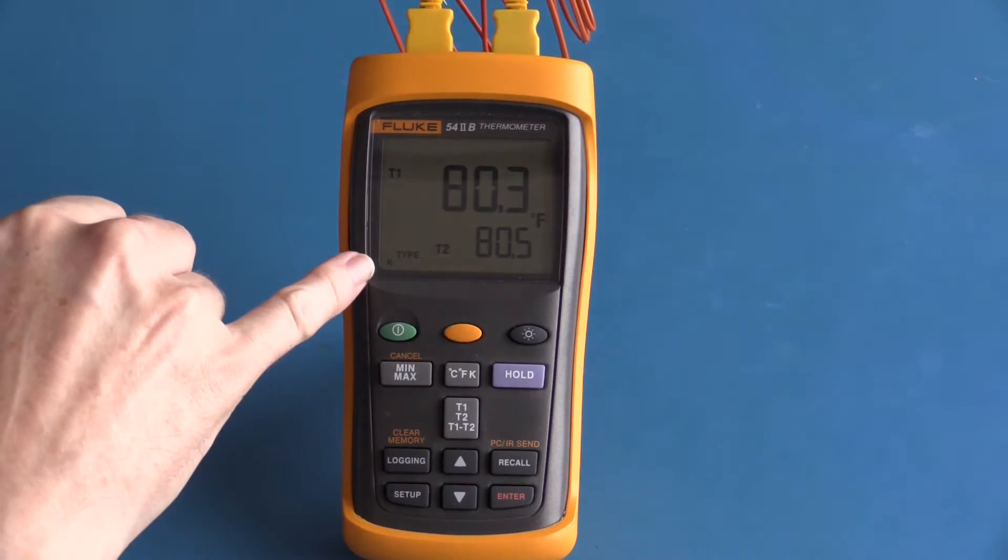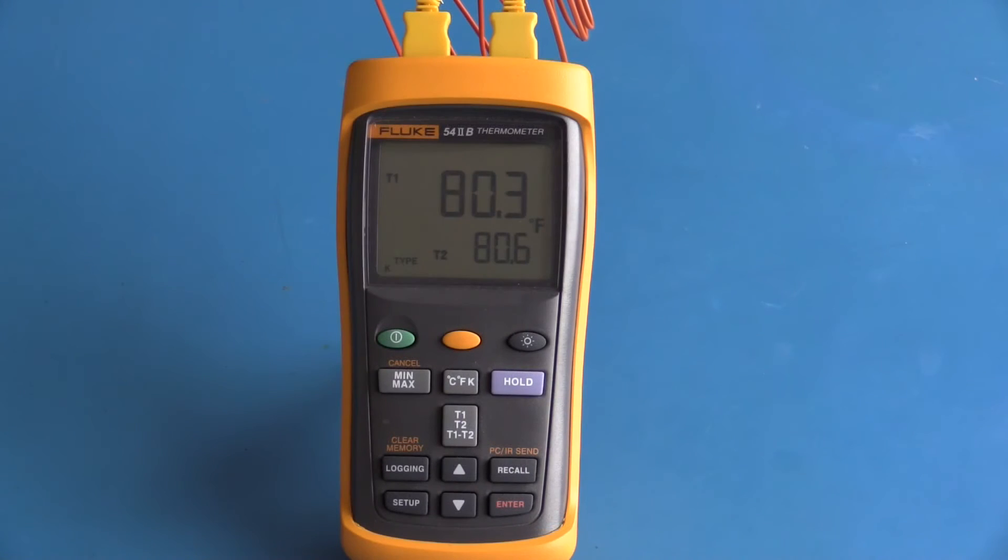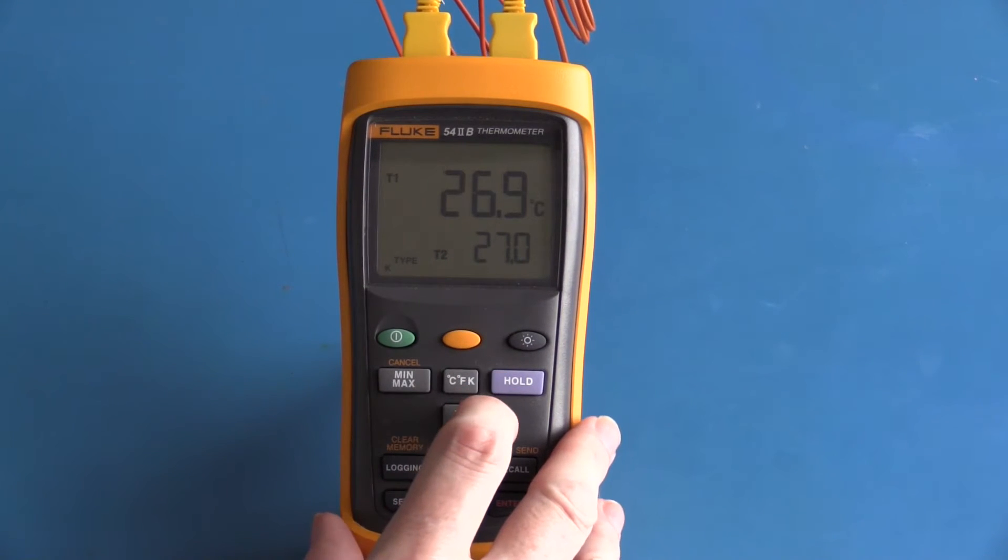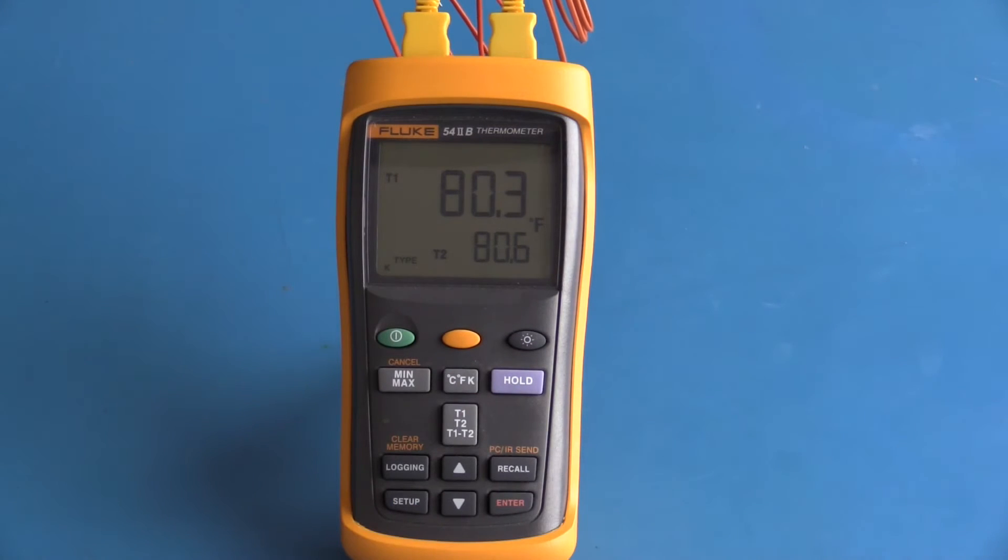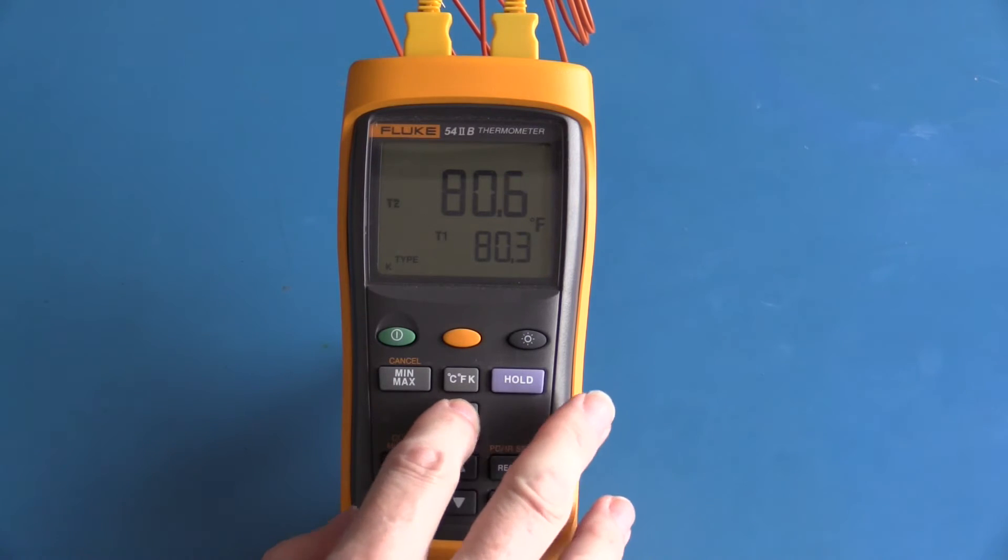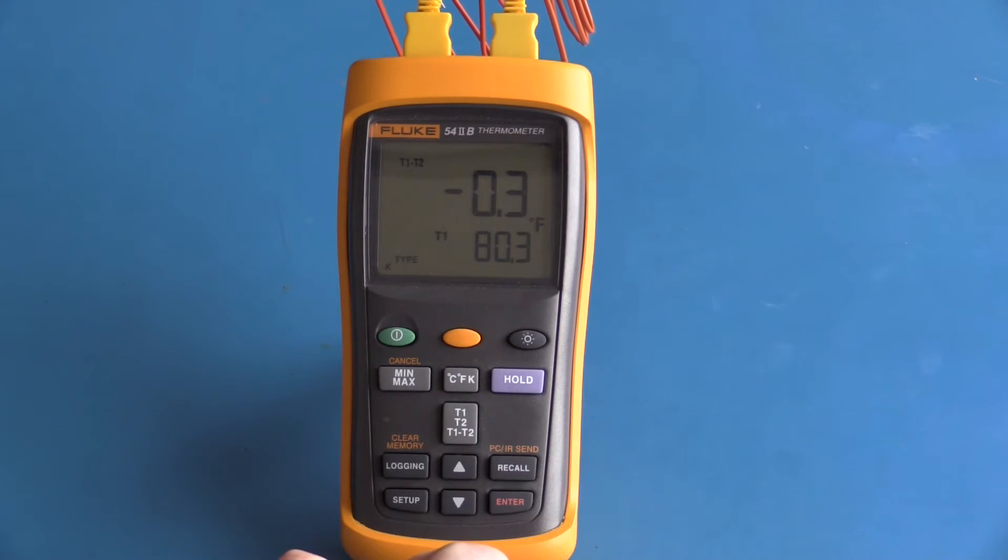Here on the left hand side it's showing that I'm using a K-type thermocouple. This thermometer provides the option to have the temperature displayed in Fahrenheit, Kelvin, or degrees Celsius. I typically prefer to use degrees Fahrenheit. The primary display can show T1, T2, T1 minus T2 with the secondary display showing T1, or T1 minus T2 with the secondary display showing T2.